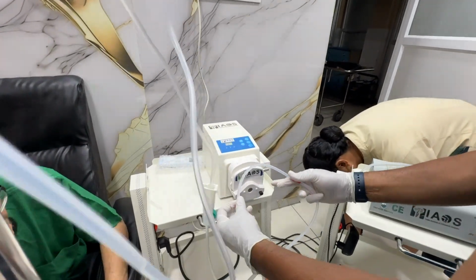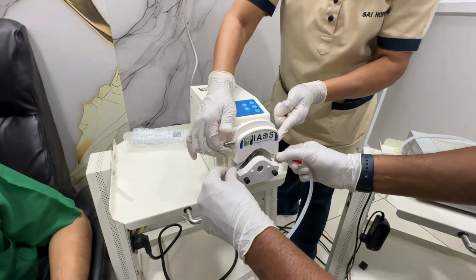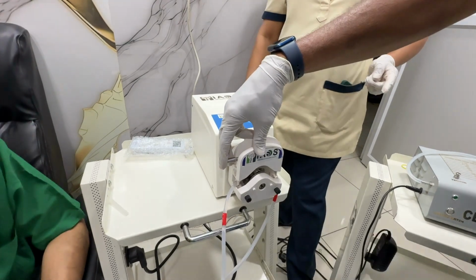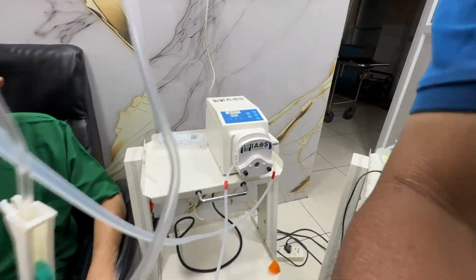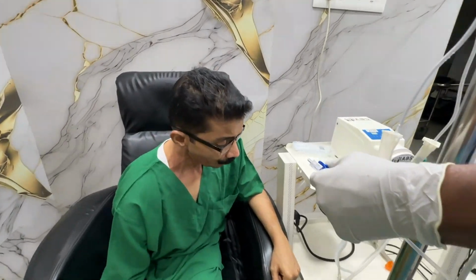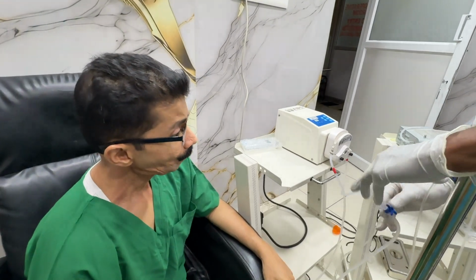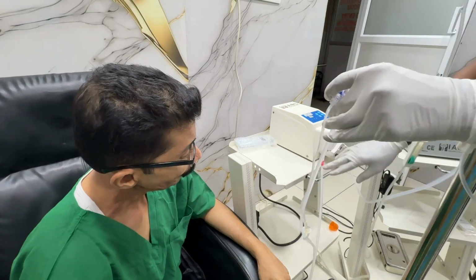The silicone donor tube has two red markings, and between the two red markings, the tube must be put into the perfusion pump. So, you have two red markings, it has to be introduced in between the two red markings. The pipes are adjusted to ensure that there are no crossovers and all connections are free and comfortable.